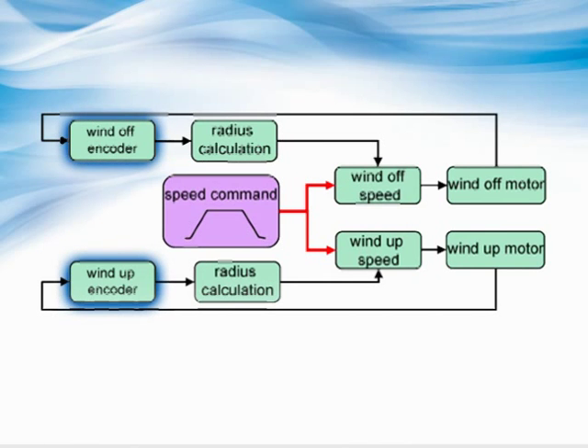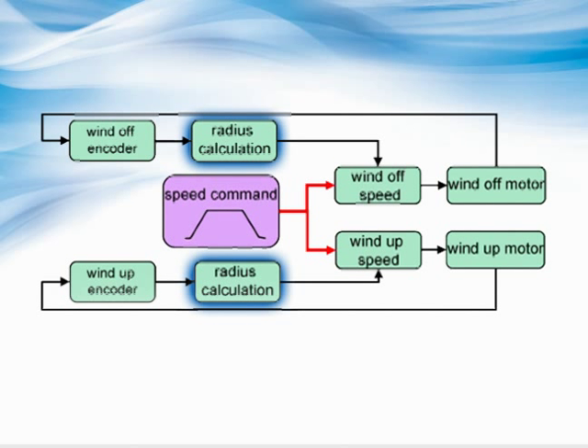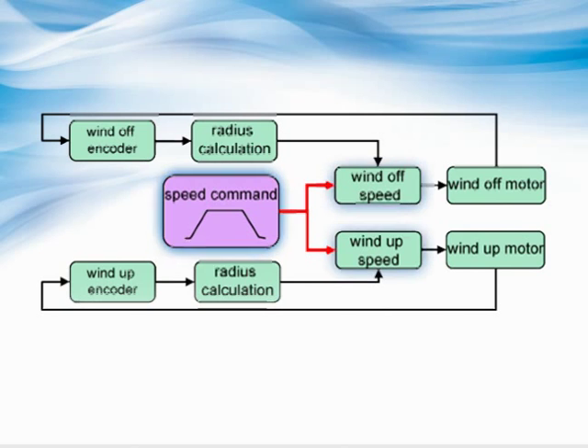Consistency of speed and tension are required to keep the material aligned during acceleration and faster winding speeds. The NJ controller and encoders monitor the winding process, calculate the radius of the wound material in real-time, and process this information to correct wind-up motor speed.